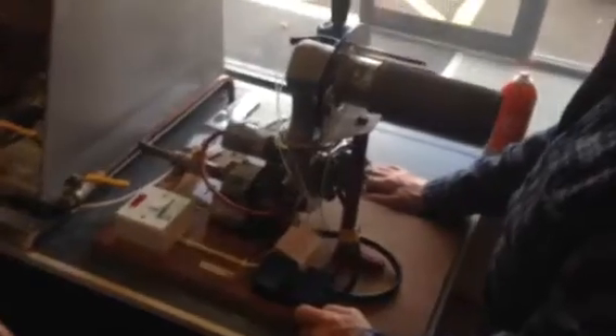And the fan ramps down like we did on the commissioning mode on that boiler. It's an idle setting. The negative pull on the mixing tube and the valve goes down as well, doesn't it? And therefore the actual diaphragm, the negative pressure on the diaphragm slackens as well, lessens, and the valve goes closer to its seat again. So the fan is the throttle. The fan is moving that valve up and down. Nothing else. So it's under negative pressure, and that's matched by the positive pressure of the gas going in.